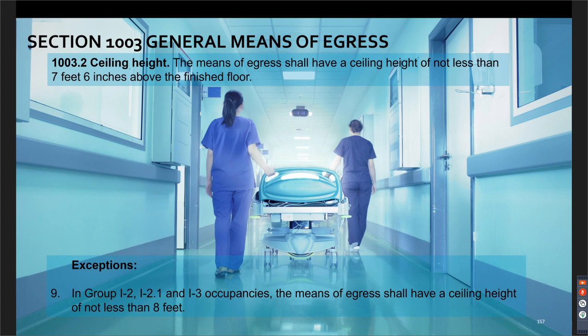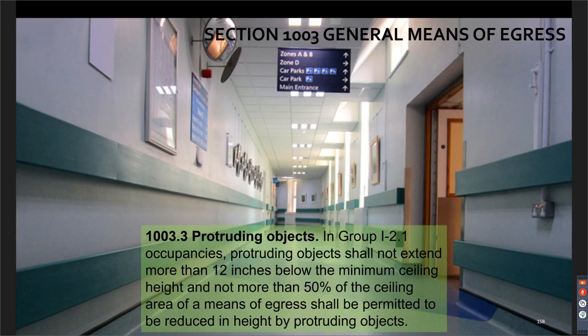Again, the timing, that it takes for relocation, it takes longer. You've got bank down capacity, if you've got smoke coming up, going up to your ceiling, having that extra few inches allows more time because it gives that smoke somewhere to go before it starts to bank down and come down to a lower level, allowing more time for relocating.